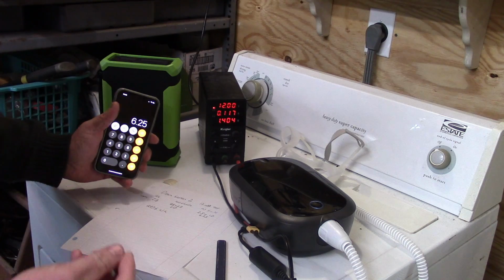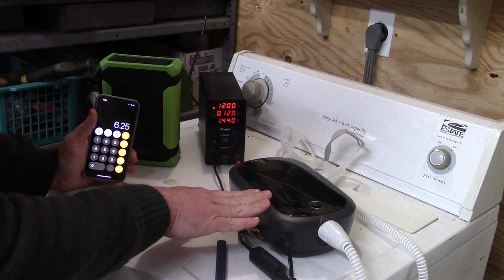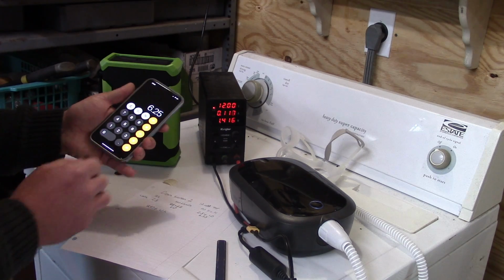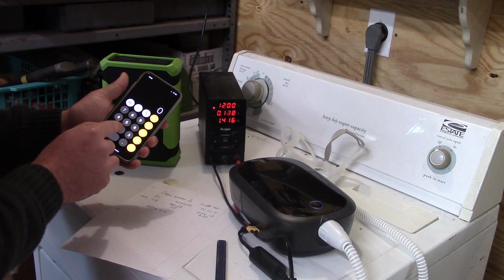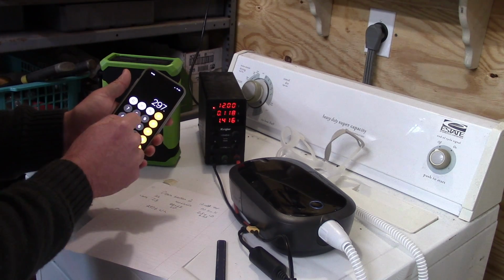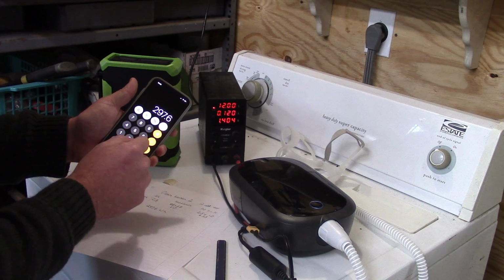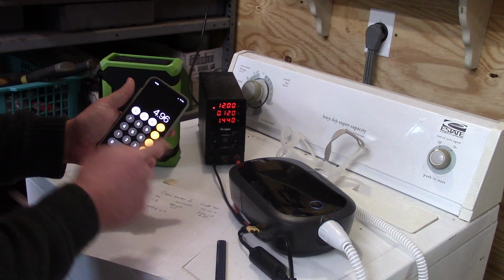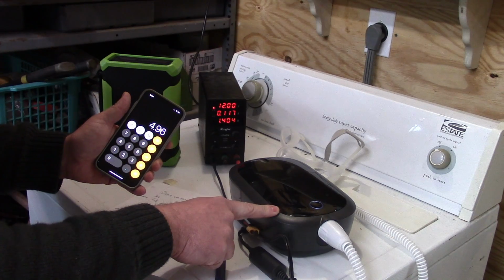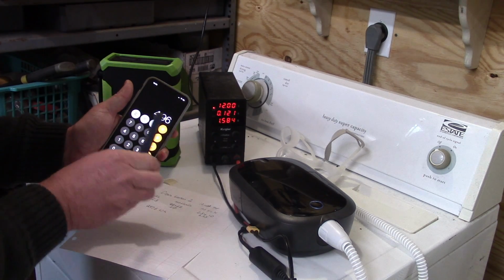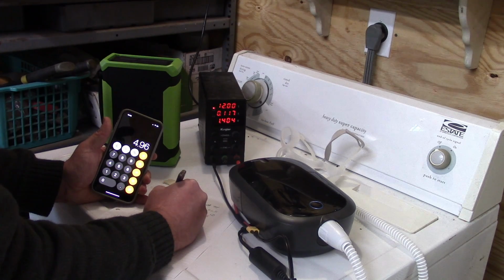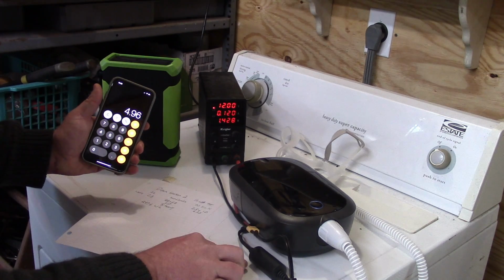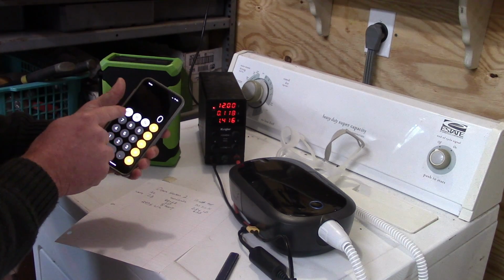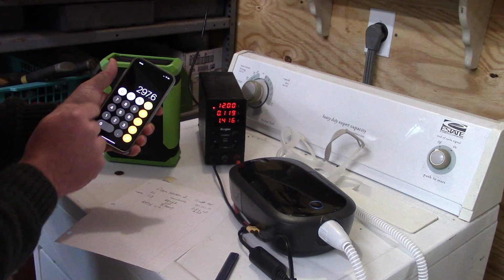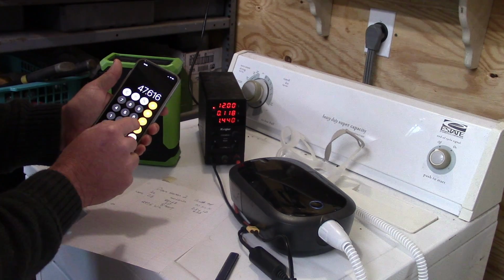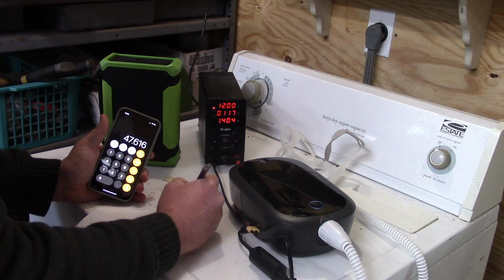So to determine how long you could run this on heat and humidity with this battery, let's just do some really simple math. We're going to take 297.6 watt hours, and we're going to divide it by our 60 watts per hour, and that means that this battery should be able to run this CPAP under these conditions with those settings for just under 5 hours. Now, if we take the no heat and humidity, this should be a really huge number. 297.6 divided by 6.25, 47.6 hours.